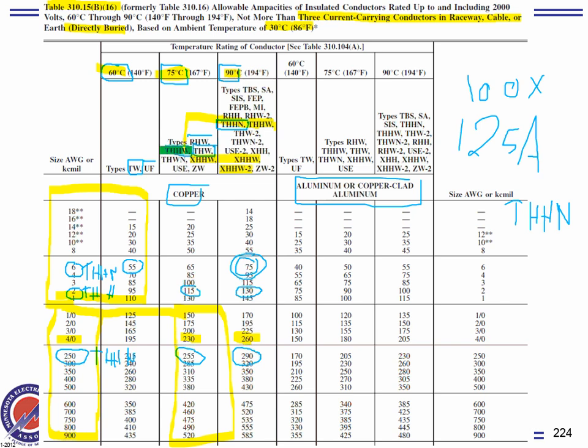So I'm going to go to which side now? It's more than 100, so I can go to 125 under 75 degree. 125, that will get me, here's 130. Can you guys see that? And that will give me number 1. 130, that will give me number 1. If it's THHN, so my conductor is number 1. So I can get my 100 and number 1 will be my conductor. Any comments, guys? Any questions? Because it's more than 100 amp, I went to 75, and that gives me number 1.